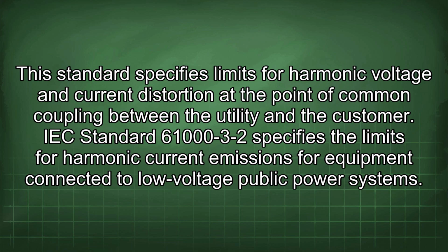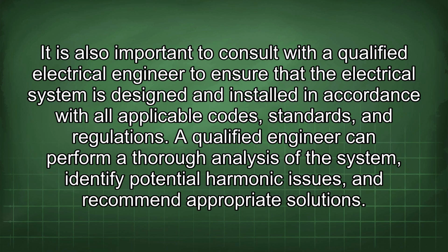IEC Standard 61000-3-2 specifies the limits for harmonic current emissions for equipment connected to low-voltage public power systems. It is also important to consult with a qualified electrical engineer to ensure that the electrical system is designed and installed in accordance with all applicable codes, standards, and regulations. A qualified engineer can perform a thorough analysis of the system, identify potential harmonic issues, and recommend appropriate solutions.